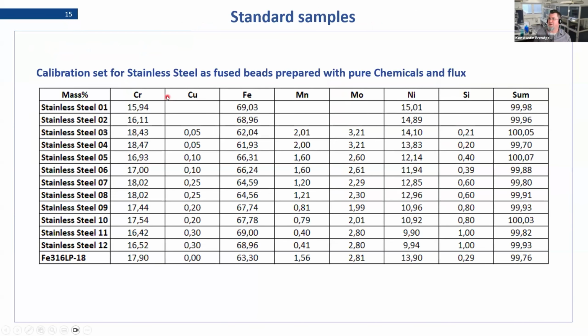FLUXANA's idea then was, with this recipe, we made a calibration set for this stainless steel in this case, but also for the other materials mentioned before. And we made this basically from pure chemicals. So we took a look at the range, and we made these 12 calibration standards just based on pure oxides to get these mixtures. And there is a standard available down here, which was used then. This was actually quite new at that point. It had just come out.